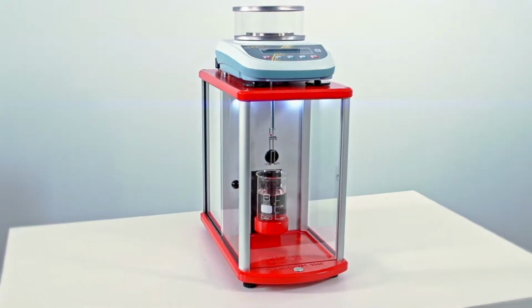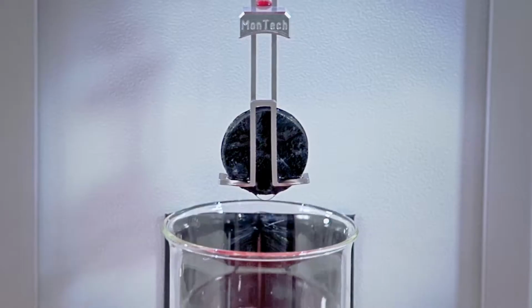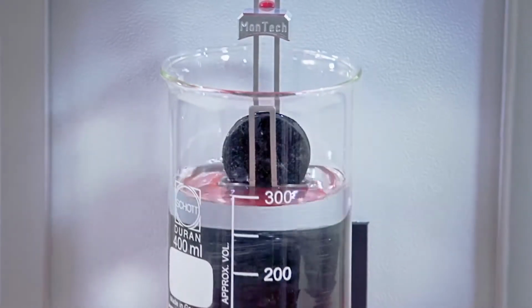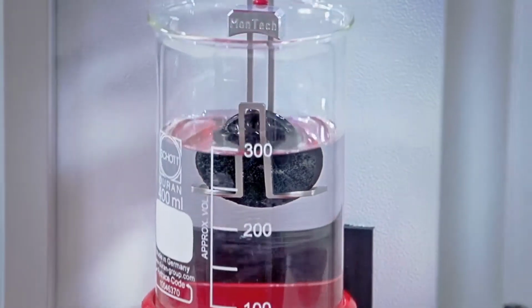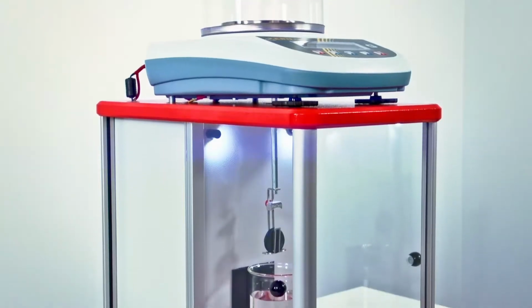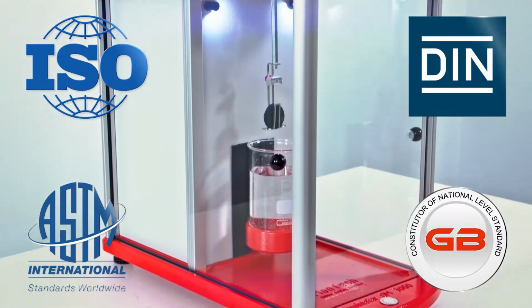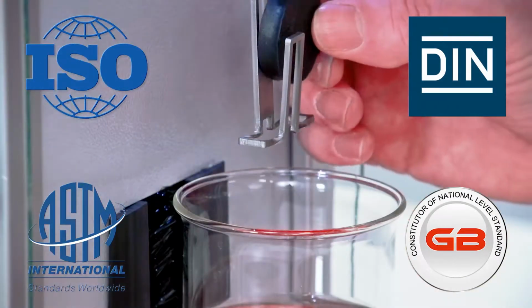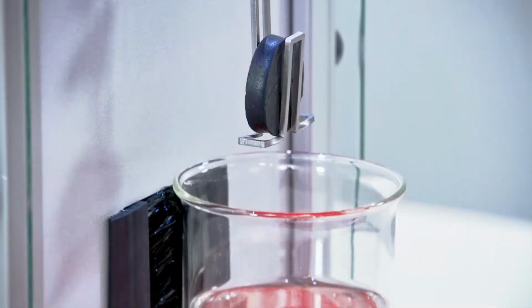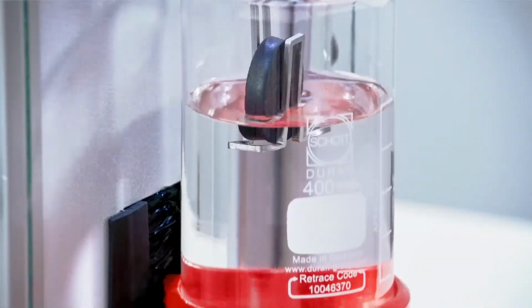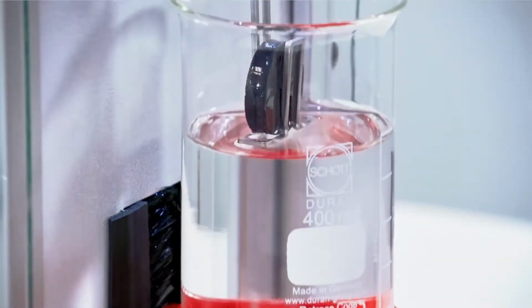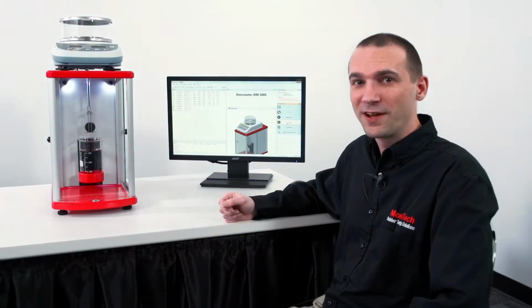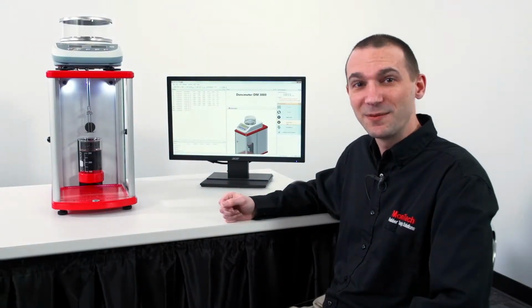MonTech's DM3000 densimeter provides accurate and rapid measurement of specific gravity for solid rubber and elastomer samples, performing up to 4 tests per minute. It meets standards required by ISO, ASTM, DIN, and GB specifications. Using the hydrostatic method, the DM3000 calculates density by comparing a sample's weight in air to its weight while immersed in liquid. Tests are semi-automated and software-guided, allowing new operators to begin testing immediately.